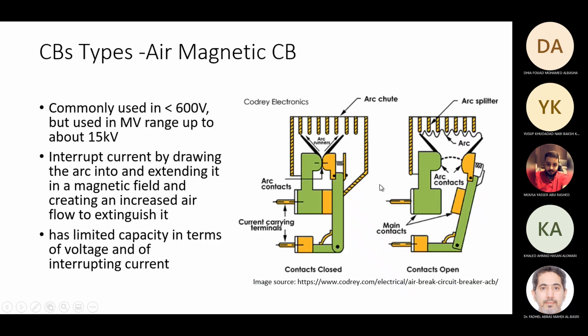For air circuit breakers, normally the air is the insulation medium, and the current passes through from one terminal. Suppose this is the fixed terminal, and this is the moving terminal. So the current passes from here to here, but also through here. When you try to open the breaker, some breakers have something called arcing contacts: the main contacts plus arcing contacts. Arcing contacts are designed to handle the arc. So the current will flow through the arcing contacts. Normally the main contacts open first, then the arcing contacts. So the arc will be split through the arc splitter until it's extinguished.